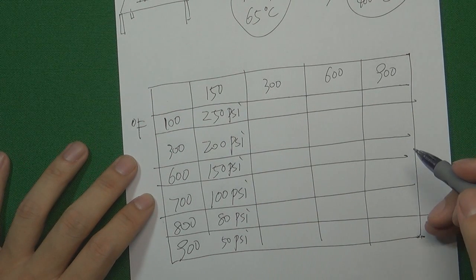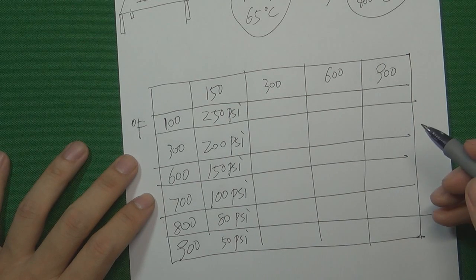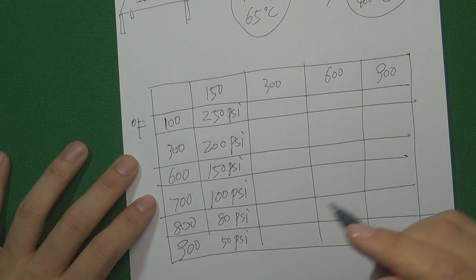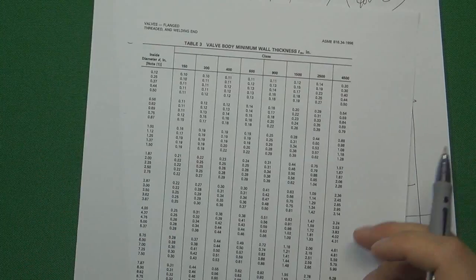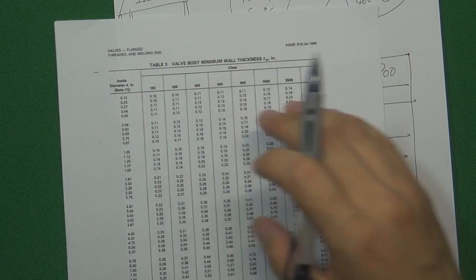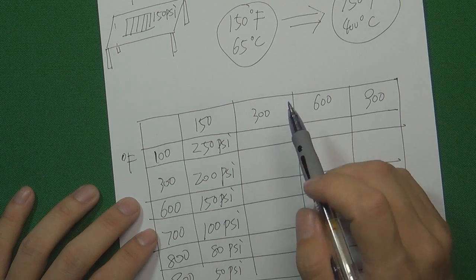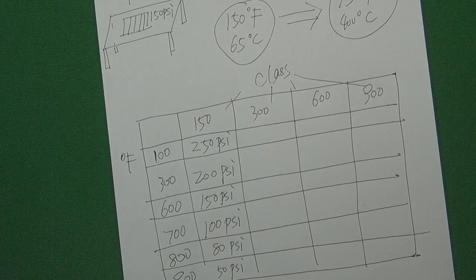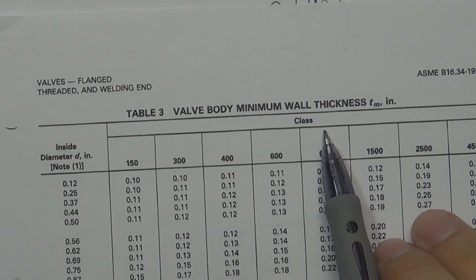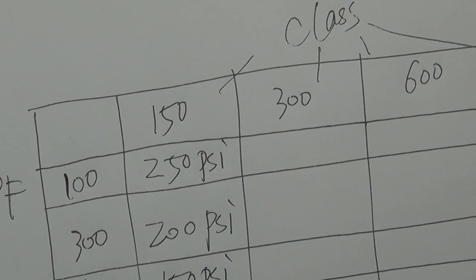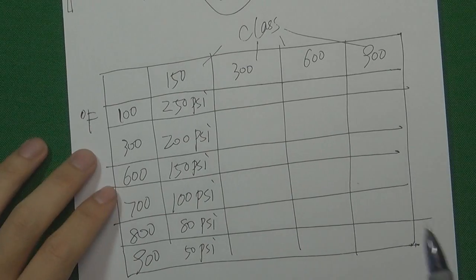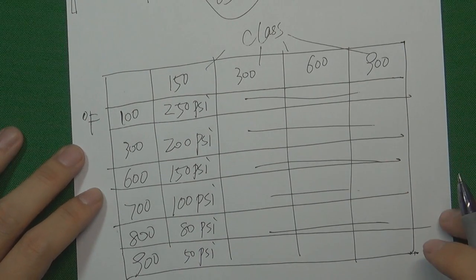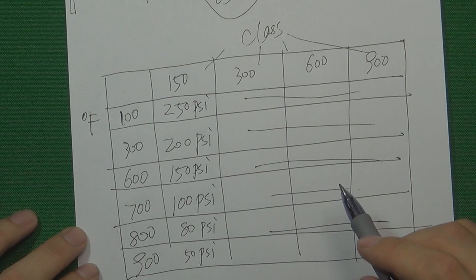So in ASME B16.34, the pioneer engineers already designed this kind of table to tell the engineer — whether designing or choosing a valve — the real pressure that the valve can hold. That is the reason why we don't put 'psi' behind the class number. We just call this number a 'class' — not a psi value. The real pressure this valve can hold requires you to check the temperature-pressure rating table. Let's look at the real ASME B16.34 temperature-pressure rating table.